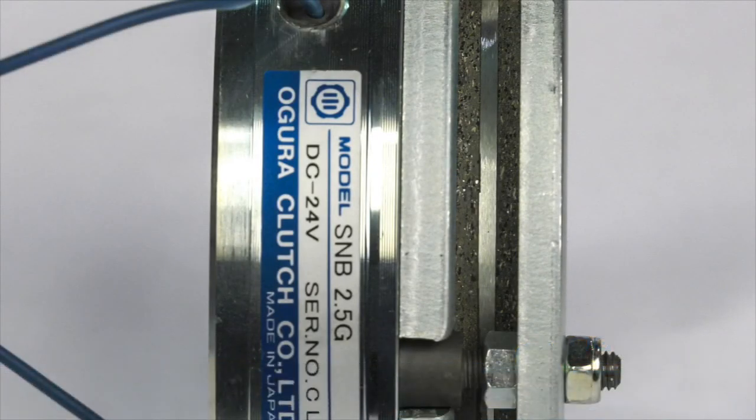Friction material swollen. Check to see if friction material has been damaged by water and is swollen, preventing release.